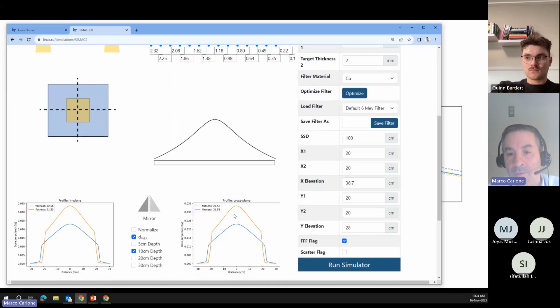The question then is, how does this affect the beam energy, and how do we quantify that, distinguishing between, let's say, the normal beam, which is the normal 6 MV beam at a 16.6 amp bending magnet current. We have our photon beam screen over here, which shows our depth dose curves, and we can look at the difference between them, because we calculate, using our beam model, which is very similar to the beam models found in planning systems, how the depth dose curves would change.